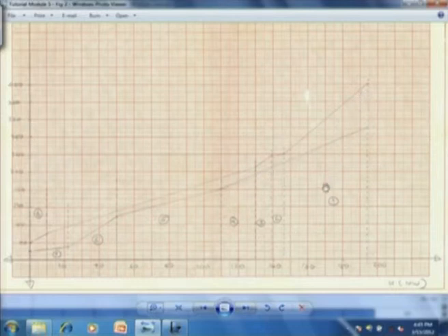Together we have 1, 2, 3, 4, 5, the longest interval, 6, 7 and 8 enthalpy intervals. Eight times either the hot composite stream or the cold composite stream changes its slope. That means the number of streams in that interval changes. Either one stream adds or one gets deleted, and therefore the slope changes. So we have identified a total of 8 enthalpy intervals.